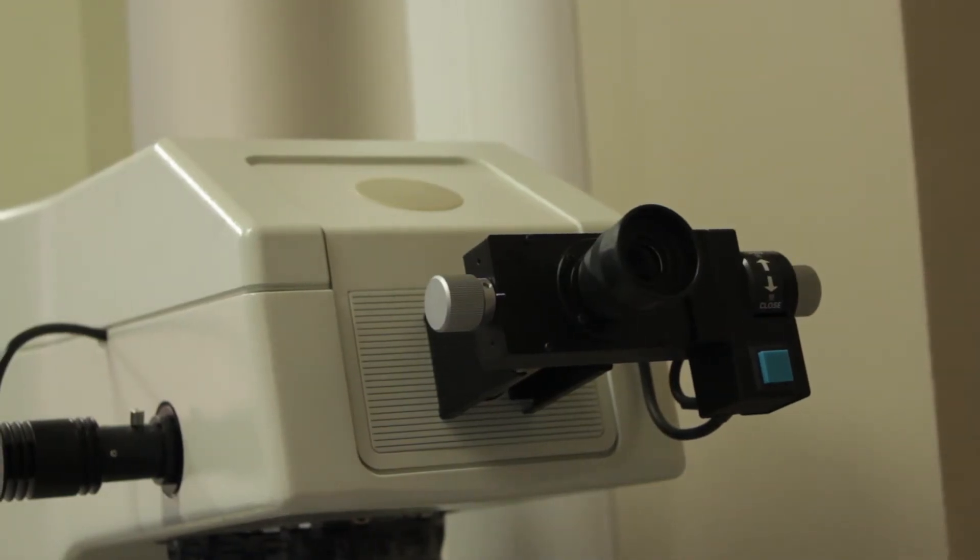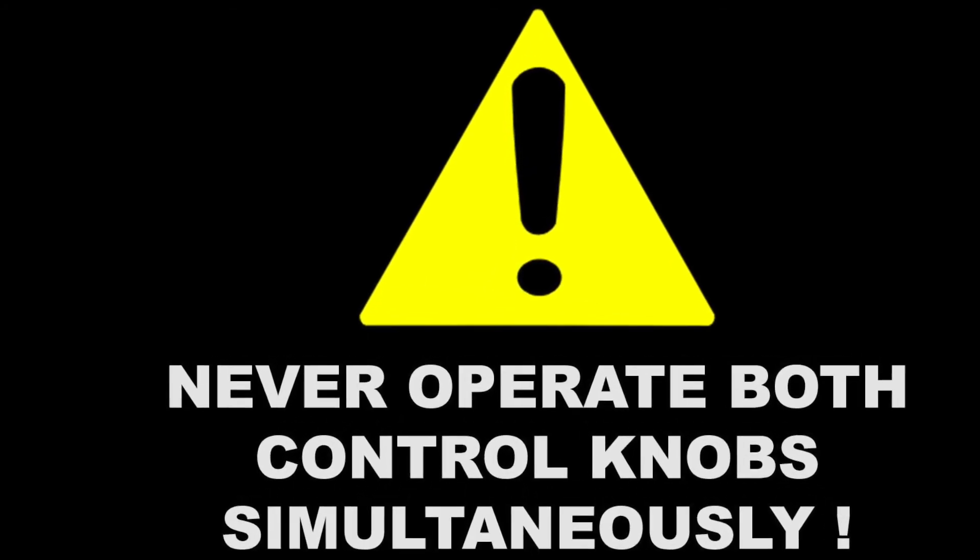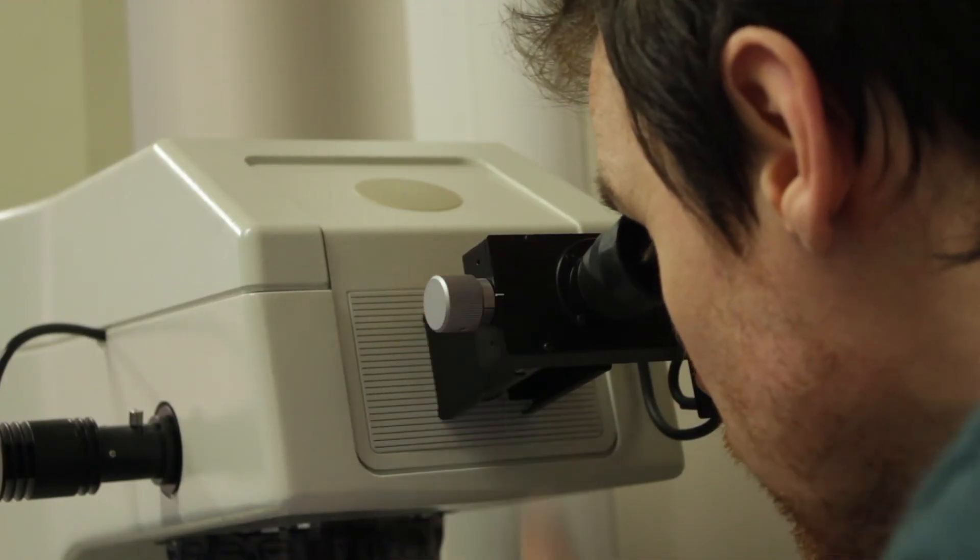Next, look through the viewfinder, but an important note: never operate both control knobs simultaneously. This can cause serious and permanent damage to the machine. First, adjust the left hand knob whilst looking through the viewfinder. This adjusts the pair of sighting lines in parallel. The aim here is to adjust the left line so that it touches the left hand edge of the diamond indentation.